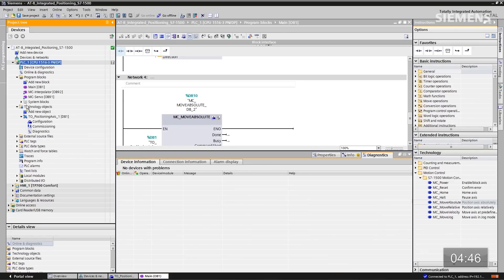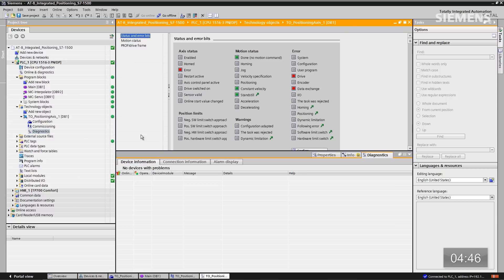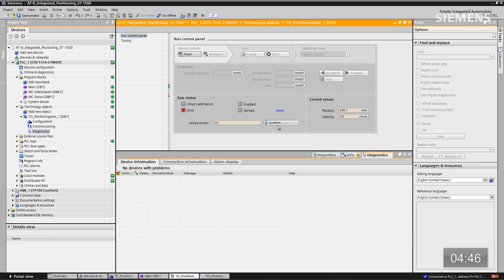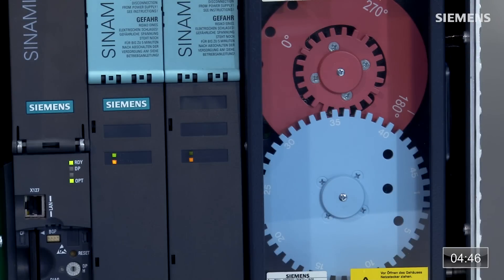Once online, in the technology object itself we'll see underneath something called Commissioning — give focus to that and double-click on it. We see some kind of error here, so underneath it there's something called Diagnostics. It shows some type of drive or data exchange problem. Let's go back to commissioning, click Confirm, and clear the error. Now I can power up the drive — our program is working just as it's supposed to. I click on home position and you can see it finding the home position. Let's do our first absolute move, and then our second reverse absolute move. I was able to accomplish all this in just a matter of minutes. Now that's engineering efficiency.